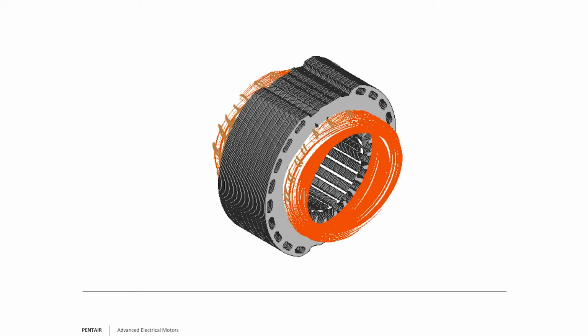They'll then press in the copper windings, as shown here. That creates a magnetic field, which is going to turn the rotor. The rotor now, again, is made of laminates, but they're cocked. They're offset a bit, because if they're perfectly straight, when you try to fire up that magnetic field, the rotor would just hum. It would not spin properly.